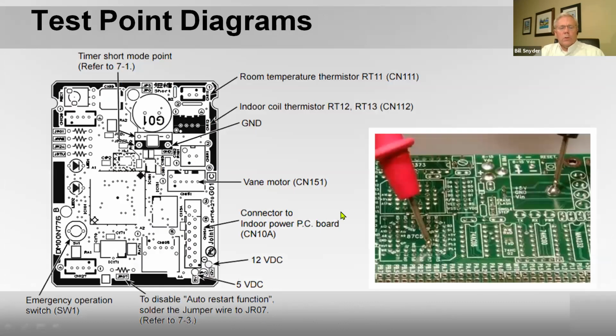It varies. Also, remember I said that some of the boards and some of the units sit on top and are upside down. Here's an example of an upside down board. This is the underneath side of the board. We have a test point diagram here that if you open it up, this diagram will look exactly like this unit sitting upside down. So it'll tell you right here, you should be looking at 5 volts DC or 12 volts DC. So you don't have to lay on your back and try to take these readings. You can take them right off the back side of the board. It's telling you there's a ground terminal here and tells you where to look for the voltages. See, this is a ground terminal here. And between here and this terminal, you should look at 5 volts DC. Between here and here, you should be looking at 12 volts DC. You know, there's your vane motor. So you'd have to look at the vane motor section to tell you how to test, but you can test it right from the back side here.